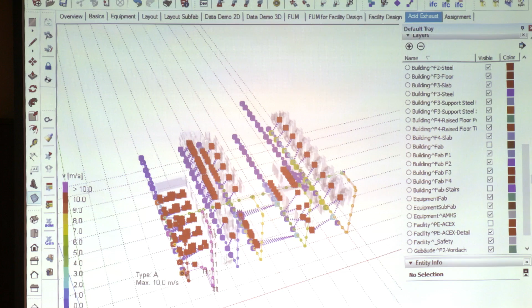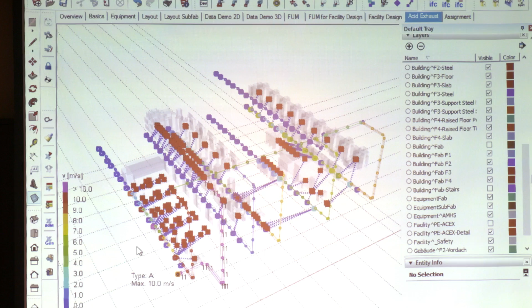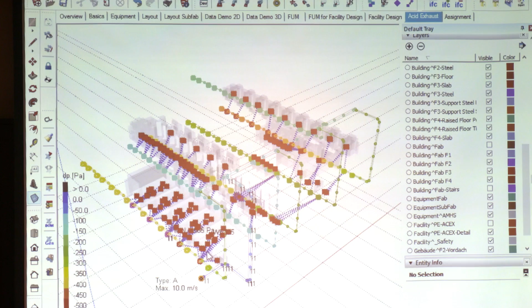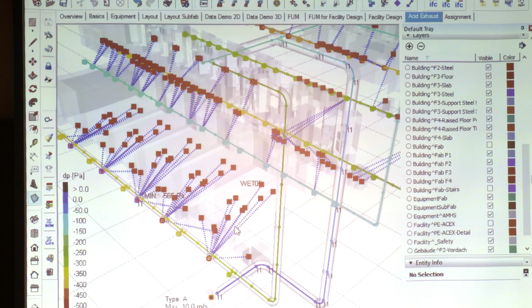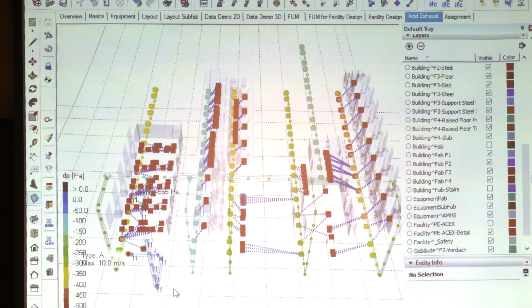But the question is not about the flow speeds. What we want to know is the pressure loss in the pipes. So let's change our visualization to pressure loss inside the pipes. This is calculated depending on the pipe elements we have. For example, T-pieces of pipe produce different pressure loss, and depending on which direction the flow comes through this T-piece, the pressure loss is different.